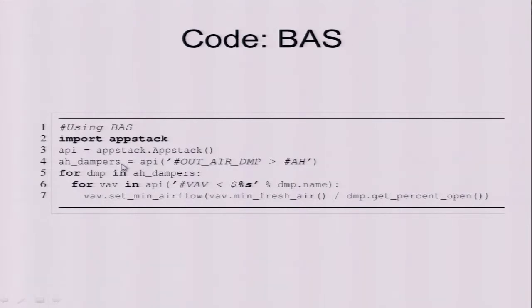You're looking to find first all of the outside air dampers for this building, anywhere you're controlling how much fresh air you're bringing in. Then for each of those, you look downstream and find any rooms fed by that air handler that might be affected by the fraction of fresh air you're bringing in, and set the airflow minimums there accordingly. That's essentially the logic here.